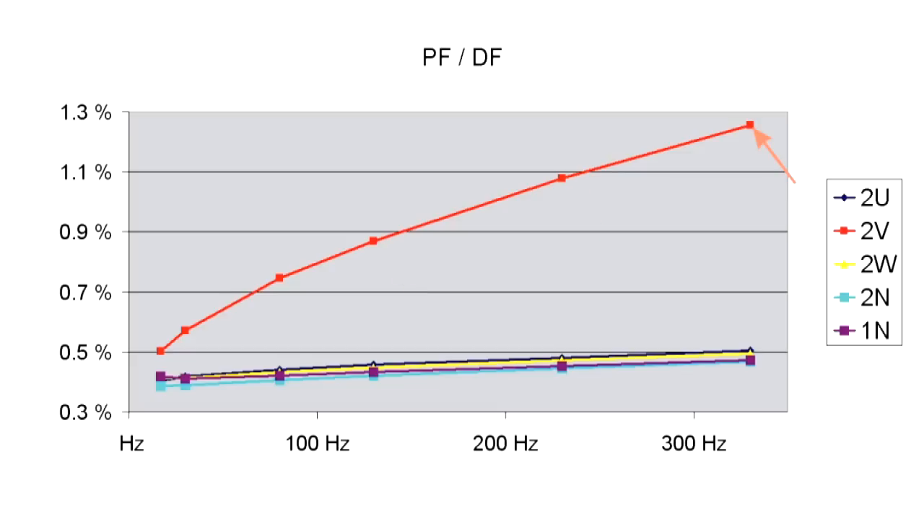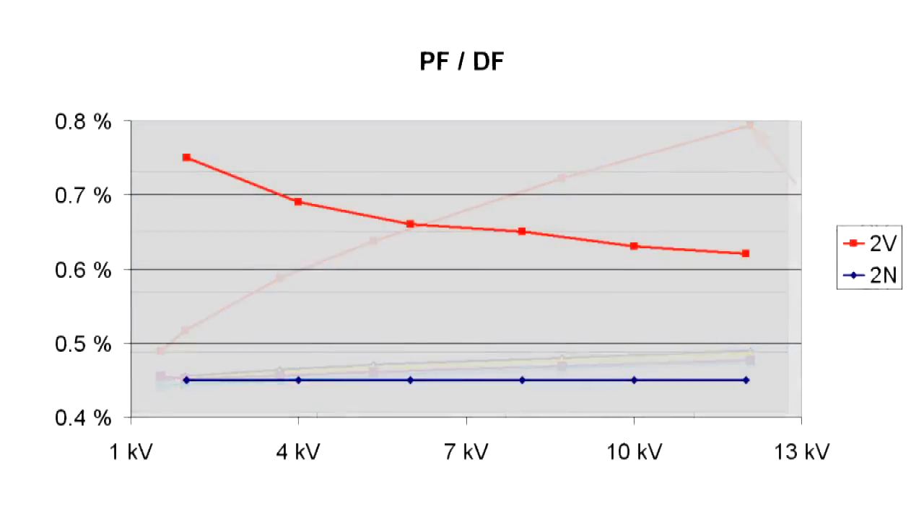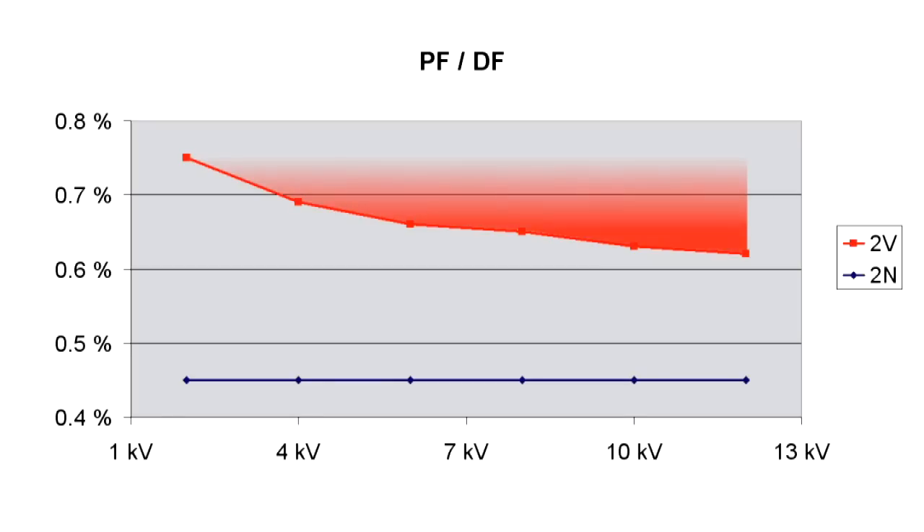This indicates that either the measurement tap or the high voltage layer is poorly connected. A second measurement at 2, 4, 6, 8, 10 and 12 kV verifies this result. The dissipation factor or the power factor of bushing 2V becomes smaller for high voltages, since the ohmic resistance of a bad contact decreases with higher voltages. This is a very dangerous situation, since a lot of heat can build up locally and result in disruptive discharges being introduced.